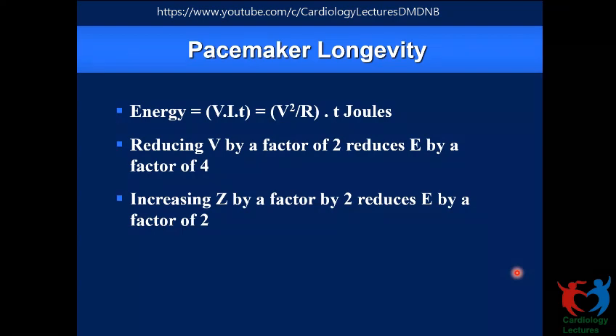And when that happens, the impedance is not just about 2000 or so. It is usually 5000 upwards of that. So in which case there is a total severance of the electrode, and then there is no current flowing. And yes, so at that time there's nothing delivered at the lead tip, so there is a loss of capture. I guess that reasonably explains.